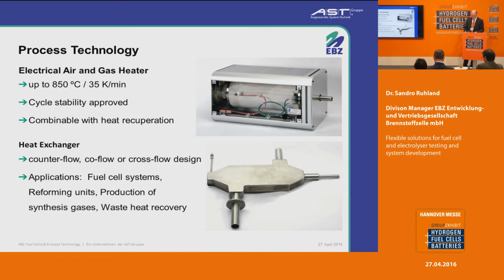For thermal management, we provide electrical air and gas heaters. They can be used for outlet temperatures up to 850 degrees, and we can use them for thermal cycling tests as well, because they can be operated with thermal gradients up to 35 Kelvin per minute. This cycle stability has also been proven, since they are already used in some thermal cycling test rigs.